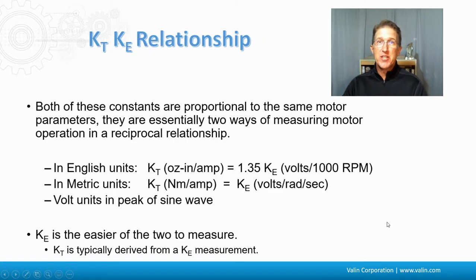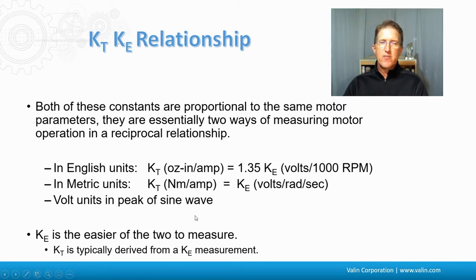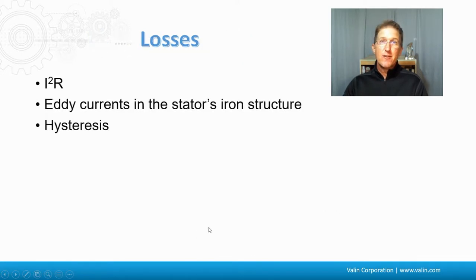There's a definite relationship between the two. Both are proportional to the same motor parameters, so they are essentially two different ways of measuring motor operation in a reciprocal relationship. The volts are expressed as the peak of the sine wave. Since the KE voltage is the easier of the two to measure, the KT is typically derived from the KE measurement. There are losses that have to be taken into account when measuring KT and KE and evaluating motor efficiency.